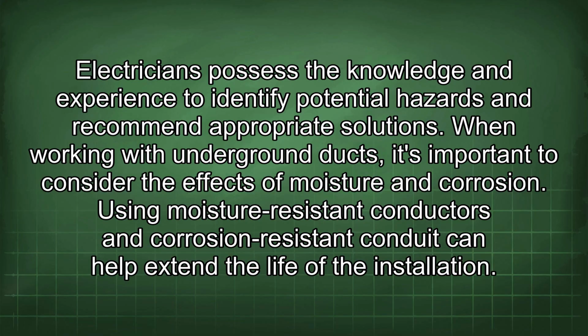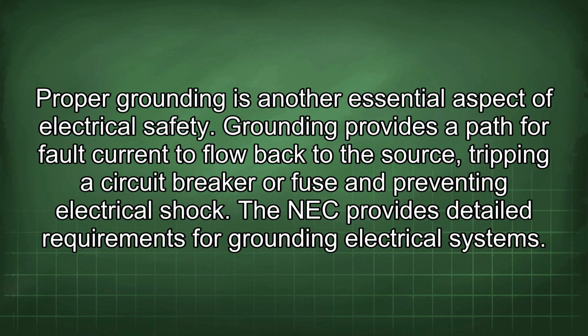When working with underground ducts, it's important to consider the effects of moisture and corrosion. Using moisture-resistant conductors and corrosion-resistant conduit can help extend the life of the installation. Proper grounding is another essential aspect of electrical safety. Grounding provides a path for fault current to flow back to the source, tripping a circuit breaker or fuse and preventing electrical shock. The NEC provides detailed requirements for grounding electrical systems.